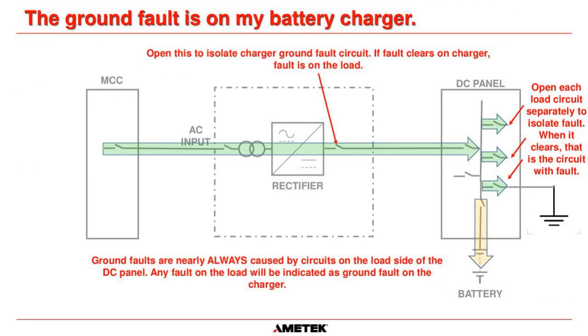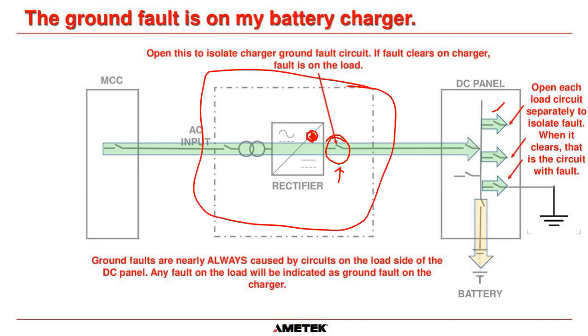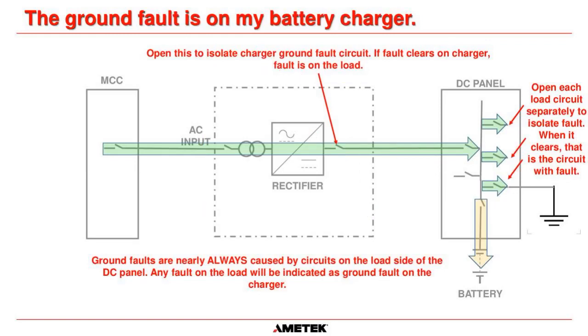Now, the easiest way to find a ground fault, now I understand in most circumstances this is very difficult to do because the plant won't allow you to switch off your load circuits. But the first thing that you need to do is open up the output breaker on the charger. Because remember, the LED and the alarm circuit for the ground fault is within the charger itself. So if the ground fault is on this load circuit here, if you disconnect the charger and the lamp goes off and it goes back to normal, you have now said, okay, the ground fault is not in the charger. It has to be somewhere upstream of this breaker here. Hopefully that makes sense. So that way you've ruled out that it's not in the charger.